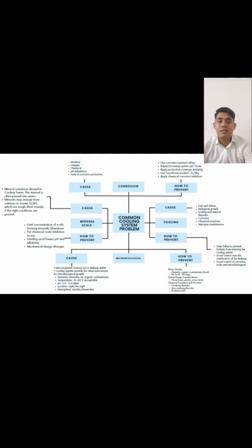And mineral scale occurs because mineral variation abounds in cooling towers. Minerals are often dissolved in water. Minerals may emerge from solution to create scale, which are thick crystals if the right conditions are present. And how to prevent it: first, limit the concentration of scale-forming minerals by blow down. Second, use a chemical scale inhibitor. The third is feeding acid to lower pH and alkalinity. And last, mechanical design change.